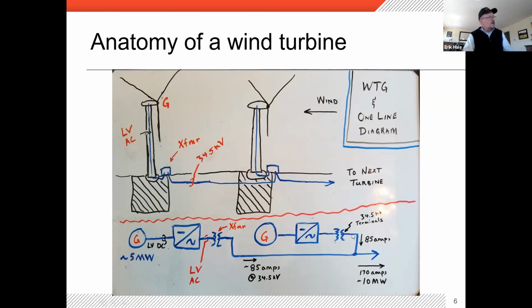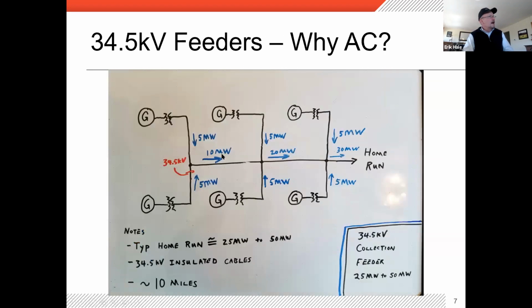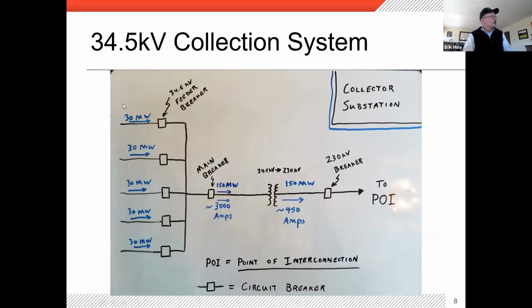You then daisy chain to the next one, and at this point you've got 10 megawatts. Continuing on from the last slide, we go further until we're up to 30 megawatts. Then we go to our collector substation with a cable we call a home run. The home run with this type of cable—think 5 to 10 miles maximum, but ideally shorter than that.